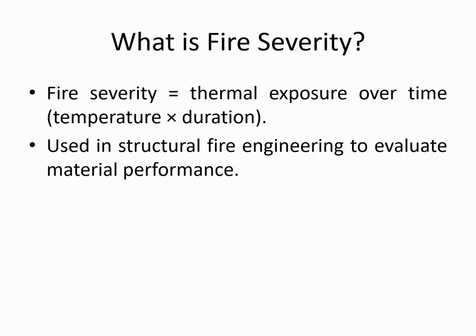Fire severity refers to the thermal exposure experienced by structural elements or material over time. In simple terms, it is temperature multiplied by the duration. The temperature multiplied by the duration is known as fire severity. It helps to evaluate how building materials will perform under fire, and it is widely used in structural fire engineering.